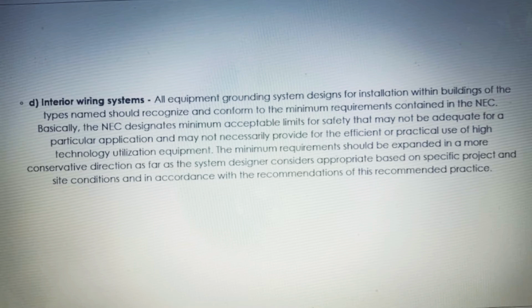For all equipment grounding for interior wiring systems, all equipment grounding in designs for installation within buildings should be recognized and confirmed to the minimum requirement of NEC. Basically, NEC designates the minimum acceptable limit for safety that may not be adequate for a particular application and may not necessarily provide for an efficient or practical use of high technology utilization equipment. The minimum requirement should be expanded in a more conservative direction as far as a system designer considers appropriate based on the specific project.